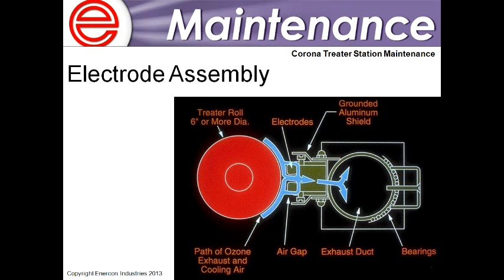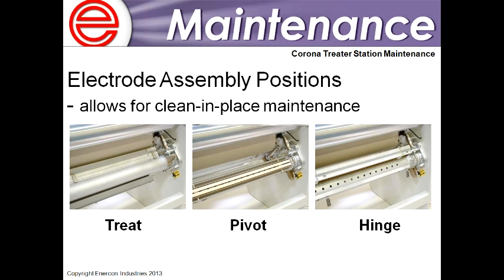And here's a slide demonstrating the suction method of the electrode assemblies, that design being to remove ozone and remove heat. But one thing to consider is it is going to be drawing in anything from the ambient air. Depending on what the environment's like, dirt can accumulate on the cooling air ports. Here's a picture showing how we design it so you can easily hinge open the electrode assembly to clean out the cooling air ports.